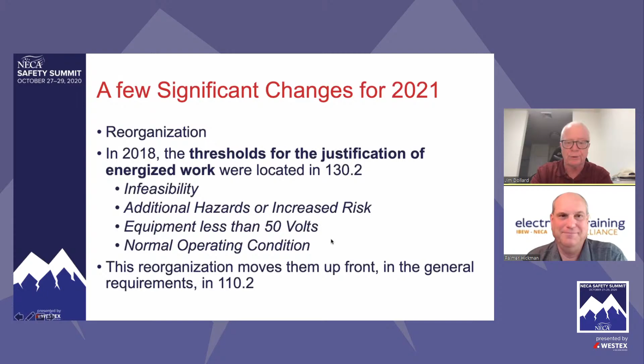So we moved the electrical safety program from 110.1 to 110.5, but the committee wasn't reducing the emphasis on the program, were they, Palmer? No, and we had to make room for stuff that come first, and we won't say one's more important or less important than the other, but the priority was to establish electrically safe work condition. So yeah, the electrical safety program, and I'll tell you, if you're looking for a place to dig in and maybe where you can do better, get into 110.5. It used to be 110.1, so we've relocated it. We've added some new requirements there as well, but it is a big, comprehensive subdivision in the standard 110.5.